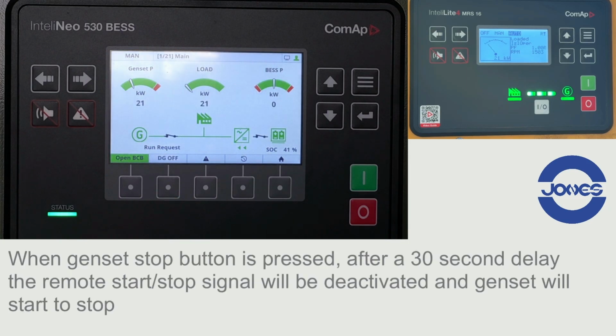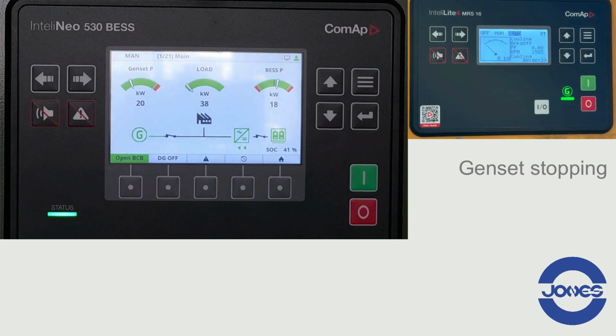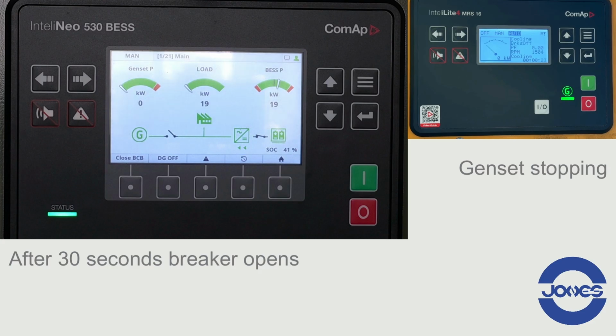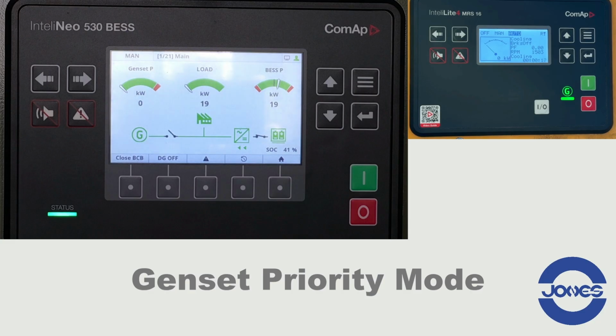When Genset stop button is pressed, after a 30-second delay, the remote start-stop signal will be deactivated and Genset will start to stop. After 30 seconds, the breaker opens and the genset is stopping. This is Genset Priority mode.